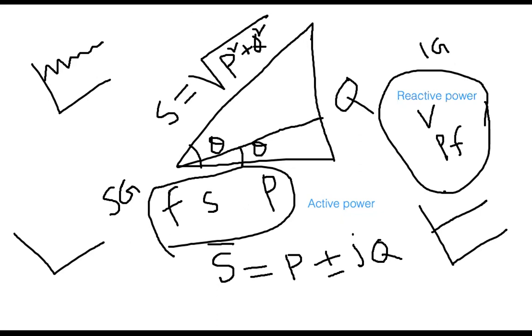Now, if your system has both a synchronous machine plus an induction machine, then you have to control all 6 variables: reactive power, voltage, power factor, frequency, speed, and the active power. So depending on the system, if it has a mixture of synchronous and induction machines, you have to make sure you are controlling all 6 parameters to properly maintain stability. Only one set is not enough.